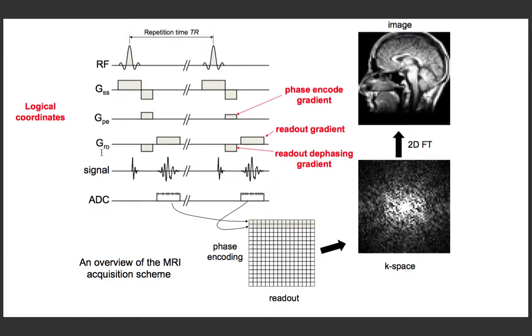This is a diagram of a pulse sequence, and this is sort of a schematic of how we do the overall acquiring. Let me point out a couple features that we see here as we walk through this. In this pulse sequence, you'll recognize already this slice selection. I have an RF pulse being played while I'm playing a slice gradient, and I have my gradient refocusing lobe. We'll imagine that this is a sagittal slice, so it's cutting through the center of the head, so I can select one little chunk through, in the right-left direction, the X direction, to make a sagittal image like this. So I'm exciting the head this direction.